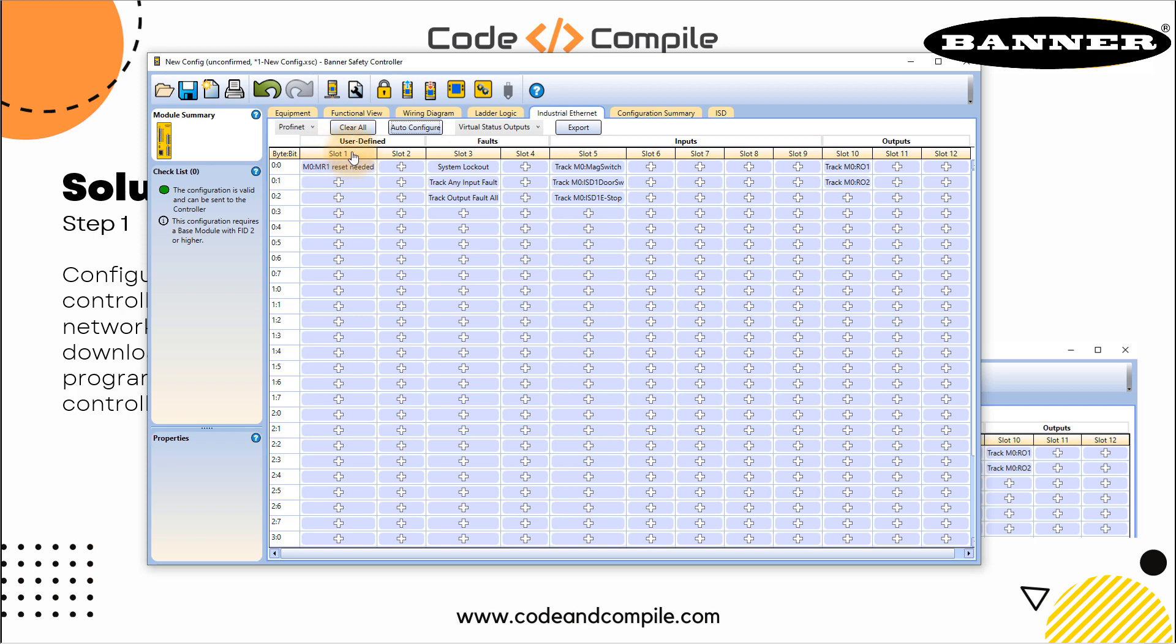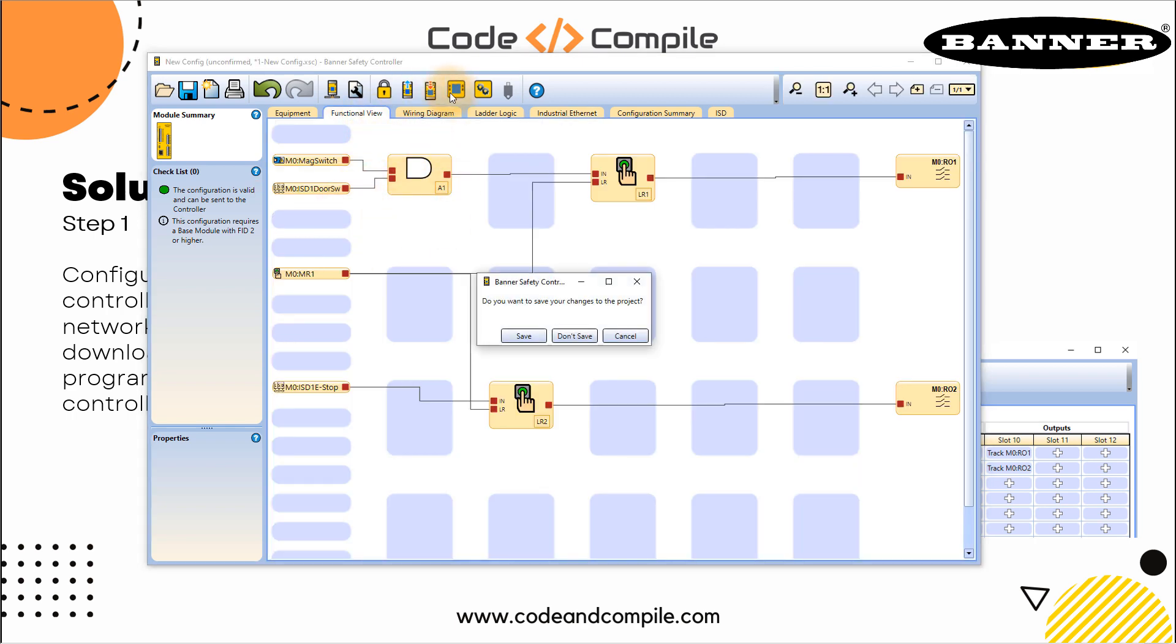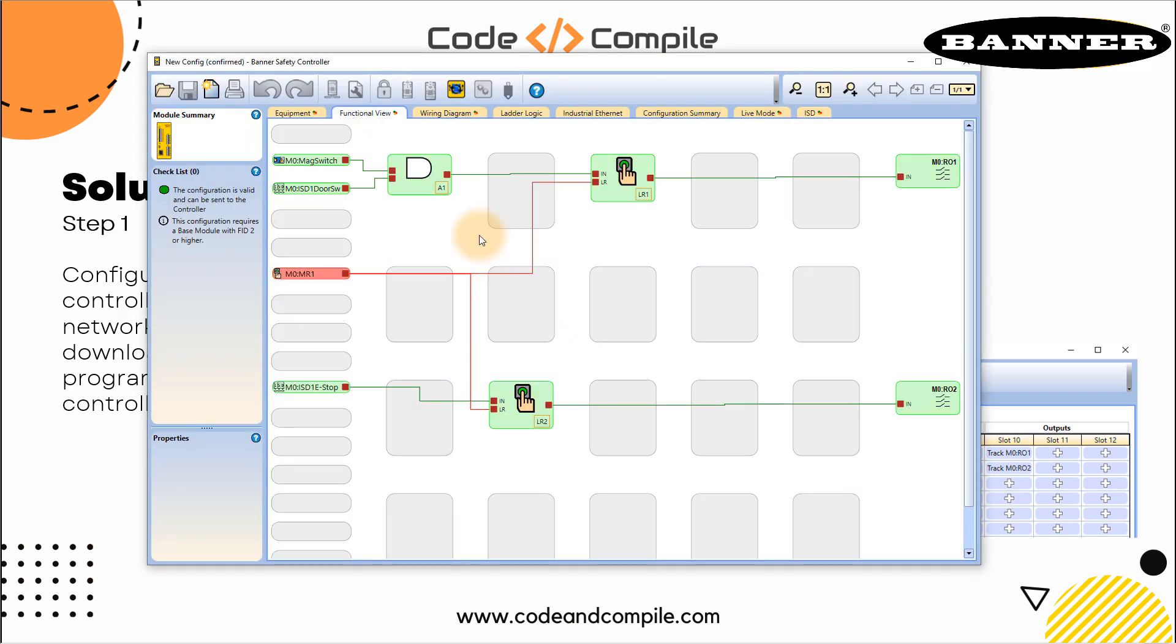For example, slot zero says M0 MR1 reset needed. We know that from this functional view when the reset is needed. Let's go online and check. So I will go online. In this case, at the moment, I don't need a reset, my outputs are working fine. Let's break the circuit.